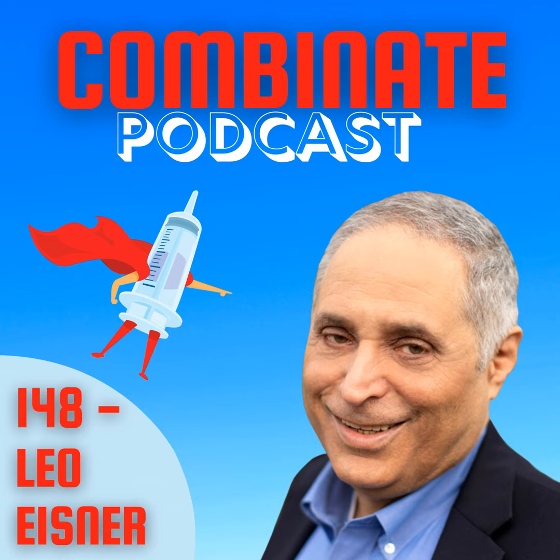I guess what I'm hearing is that for product requirements, if you have a bespoke, obscure device touching a few different standards but not really falling into a category, you know you have some characteristics defined in other standards that you can pull from. Those could help establish your acceptance criteria, test method, how you set up your fixtures, and so on. That's where in your PRD you'd document the requirement, noting the source of the acceptance criteria is that standard, and so on.